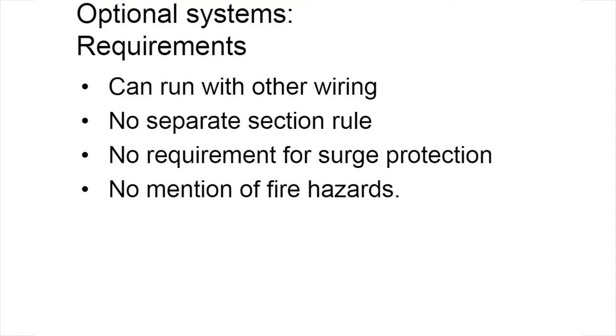Optional systems can be run with other wiring, just like legally required standby. There's no requirement for separation for optional systems or legally required standby, and that's in contrast to the requirement for emergency systems. The NEC, for example, would allow legally required standby wiring and optional wiring in the same raceway, enclosure, or wireway. There's no requirement that the optional standby circuits be served from anything separated from anything in a switchboard or switchgear. And there's no requirement for surge suppression on the panels and no mention at all of fire hazards in Article 702.